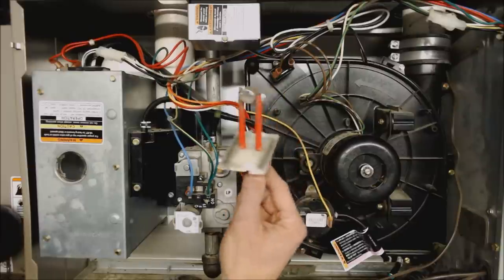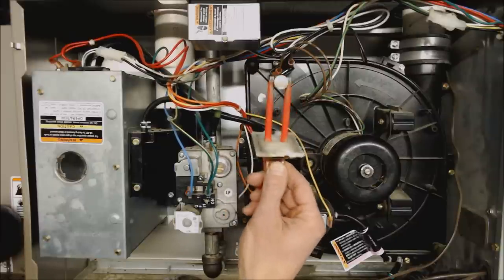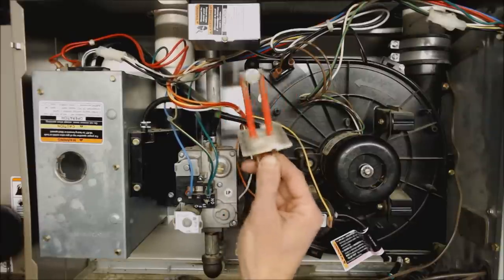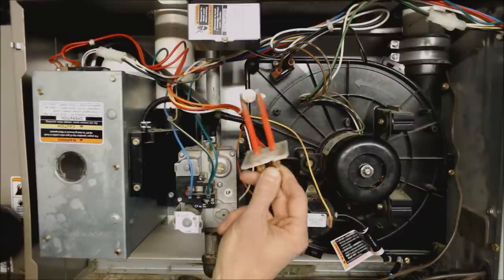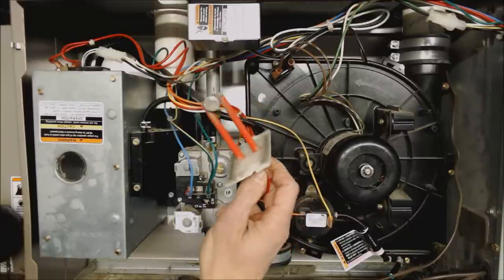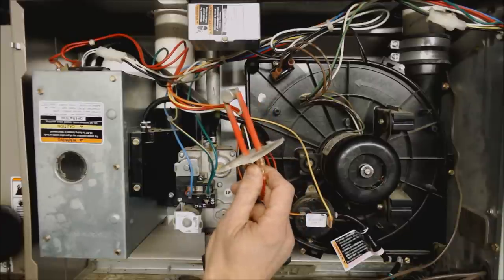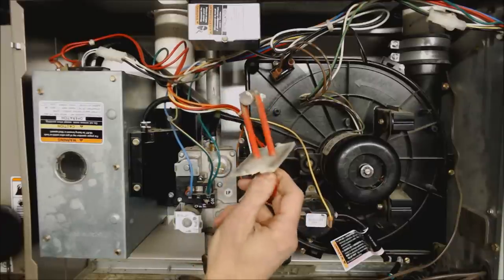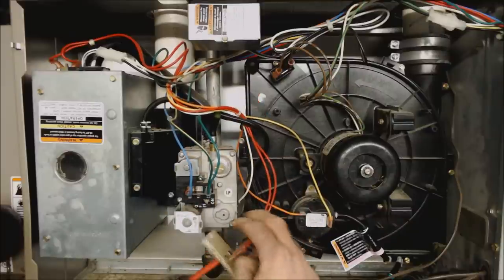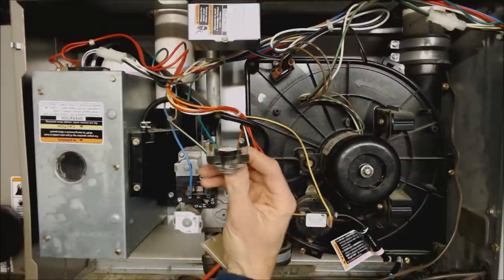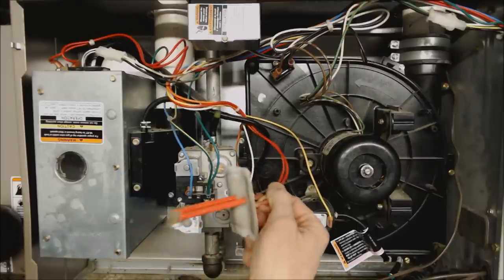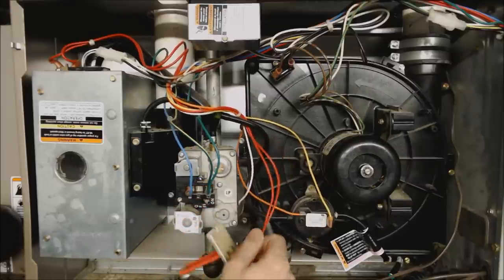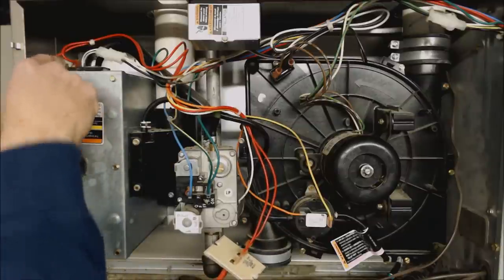So what I did right here is this is one of the reasons - it could be a safety sensor that's a problem. So I pulled this out. This actually goes back here and it goes into the heat exchanger area and it's the high heat temperature sensor, otherwise known as the high heat plenum switch. So it could look like this. It could also look something like this.